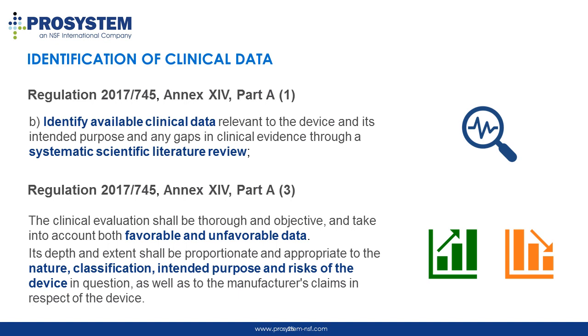Regarding the identification of clinical data in Annex 14, it is stated that available clinical data to cover the intended purpose of the device, as well as any gaps in clinical evidence, can be identified through a systematic scientific literature review. In addition, it is made clear that the clinical evaluation should be thorough and objective, and take into account both favorable and unfavorable data. The clinical data should also be appropriate to the nature, classification, intended purpose, and risks of the device in question, as well as cover the manufacturer's claims.